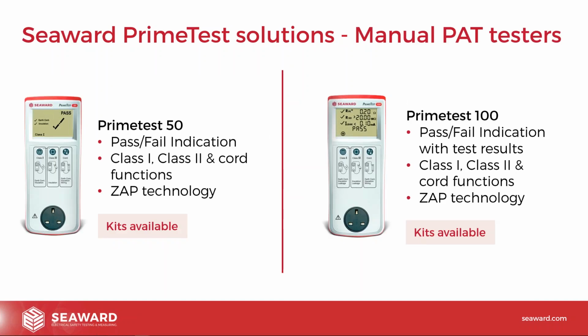So I'll go through very quickly the range of testers that we've got here, starting with the Primetest 50. The Primetest 50 is a very basic battery powered tester, and it gives you a ticker across, as you can see on the screen. So it's ideal for doing what I call enhanced visual inspection. If you're getting new equipment and you just want to check it before you put it into service, but then it's going to be checked again as part of the main PAT testing, maybe annually or something like that.